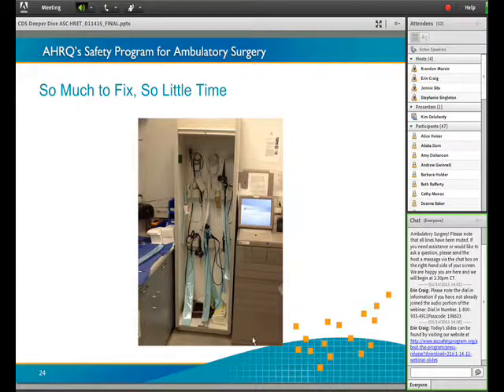There should be nothing on the bottom of a well-ventilated, closed cabinet, where all scopes hang totally straight down and all movable parts are removed and put on a separate shelf so they can dry effectively. All these loops and things pose a problem in the event there was liquid or fluid still left in the chamber, which there shouldn't be, but things don't always happen the way we think they do. That's how transmission of organisms occurs and people get sick.